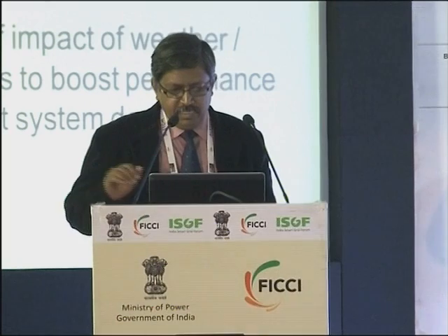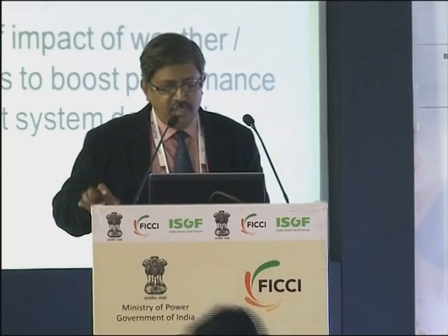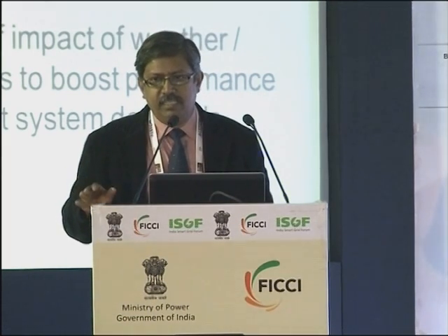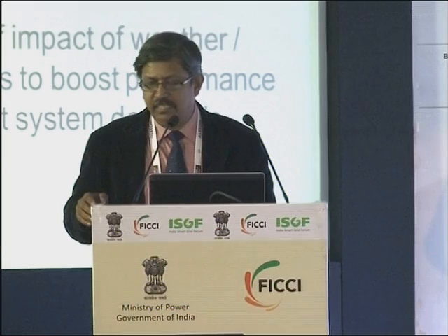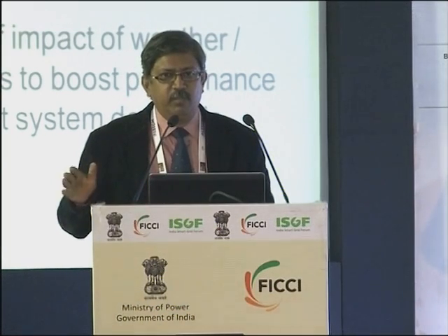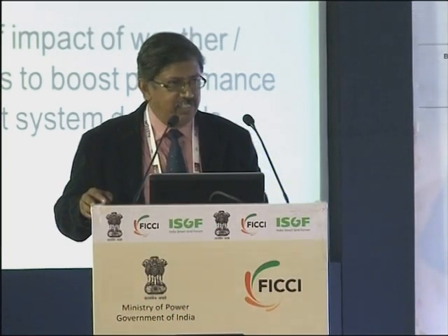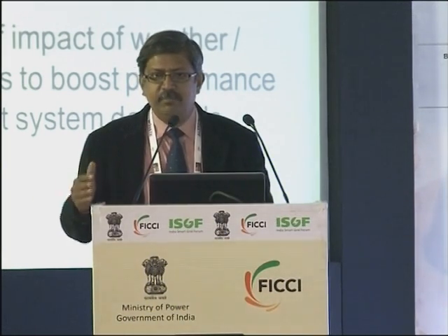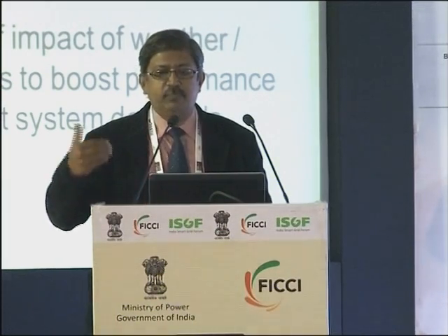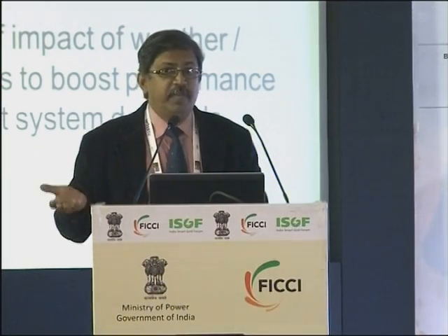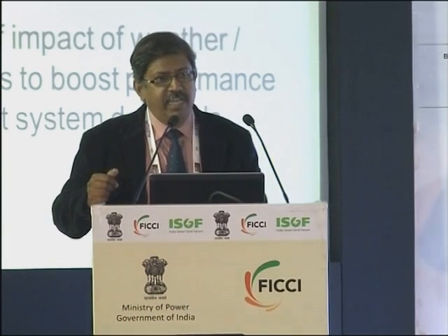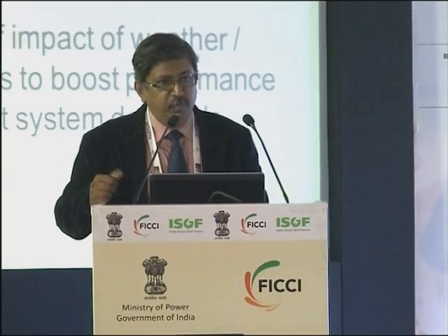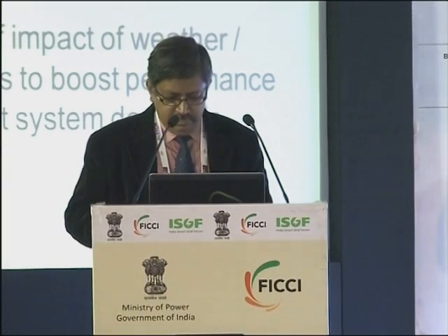The other aspect is to take cognizance of the impact of weather. Wind is one of the key things that determines the rating of a transmission line. And we all know that during windy conditions, the wind farms generate more power, and that's the time you need to transmit more power. So why not make use of this fact and increase the line rating whenever wind speed is high.